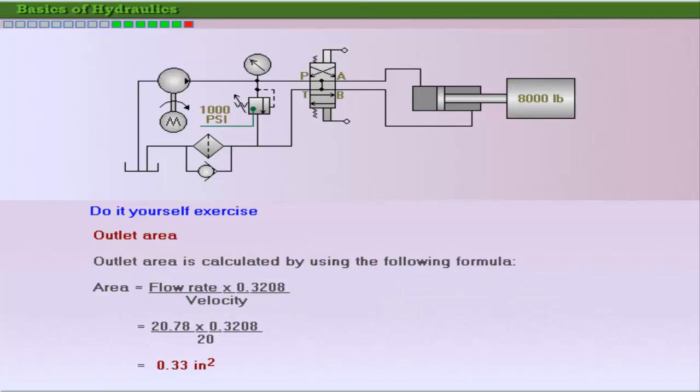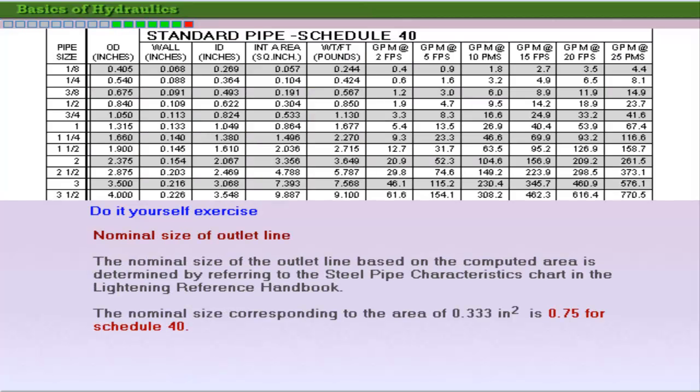Calculate the area of the pump outlet to determine its nominal size. Find the nominal size of the outlet line from the steel pipe characteristics chart in the Lightning Reference Handbook. The nominal size for the pump outlet line corresponding to the computed area of 0.33 square inches is 0.75 for schedule 40.